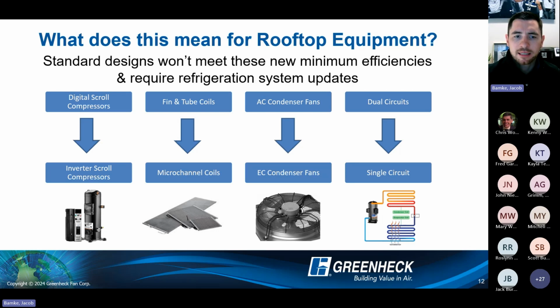Microchannel coils, you get a little bit less pressure drop through the coils. They give you better heat rejection with a smaller coil. You use less refrigerant, so some benefits with the microchannel coils that we've seen. And then AC, more on-off type condenser fans, really getting towards that modulating condenser fan. So EC or VFD driven condenser fans, extremely important not only for efficiency, but if you do ever have applications where you talk about hot gas reheat, that is extremely important to have a modulating condenser fan so you can maintain better reheat capacity in your system.